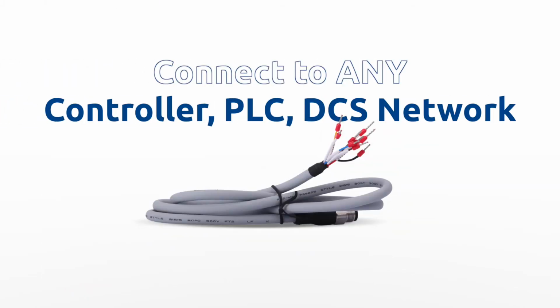These sensors are provided with an 8-pin quick adapter bulkhead and flying lead cable and operate on a conventional 24 VDC power supply, providing fully integrated dual 4 to 20 mA and RS-485 Modbus outputs. This format enables transmittance of the ORP and pH values directly to any existing display, controller, PLC, or DCS network.